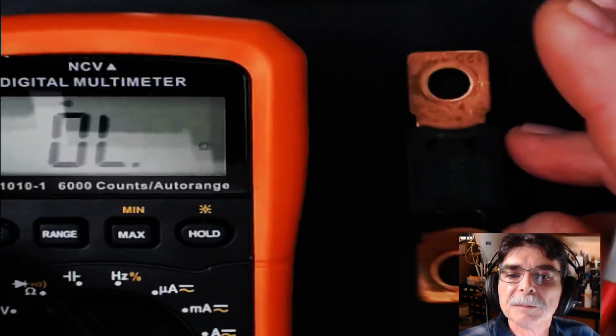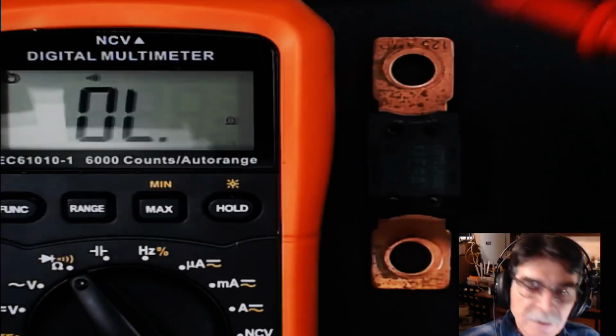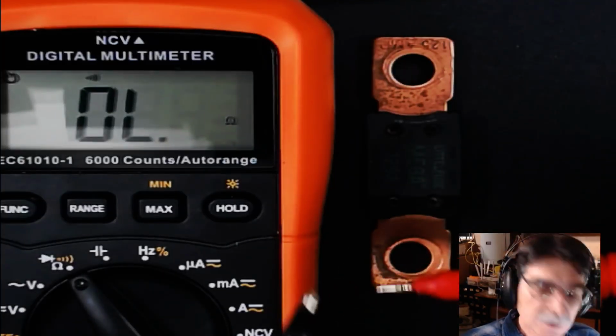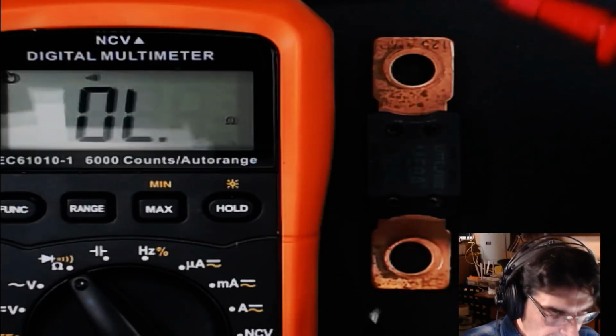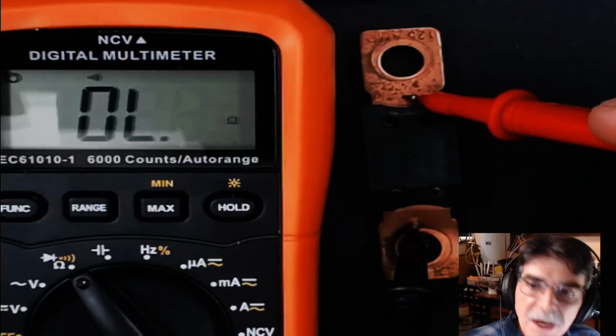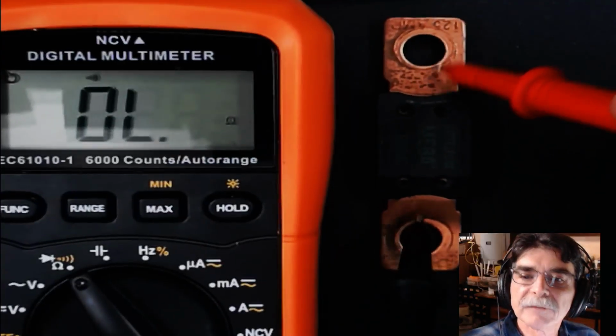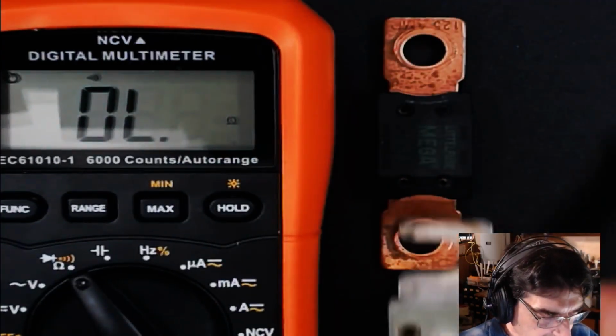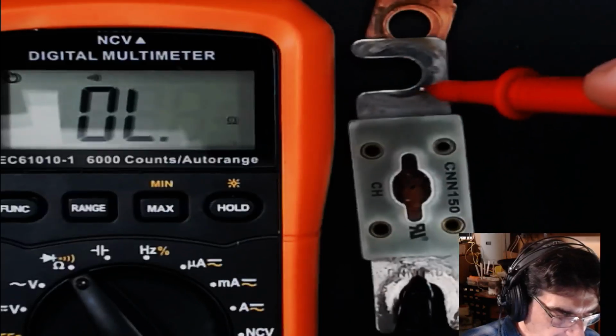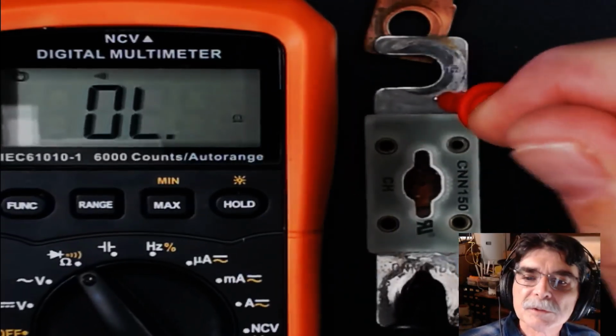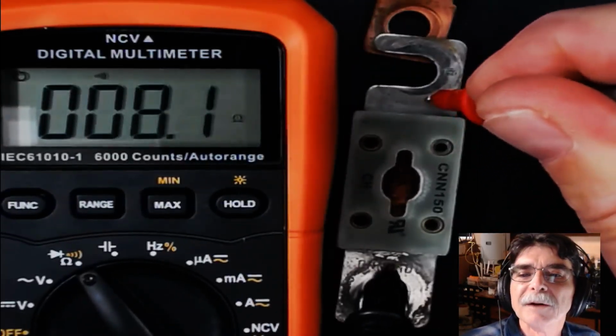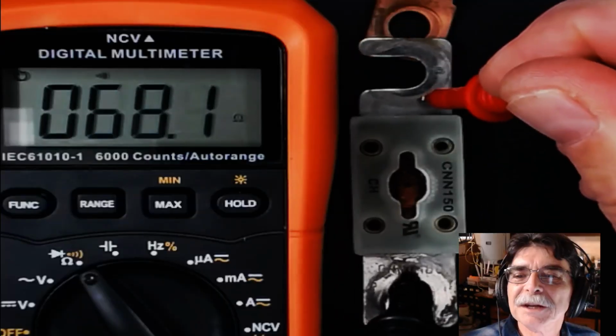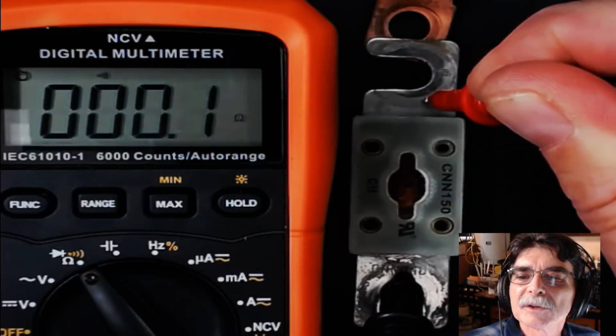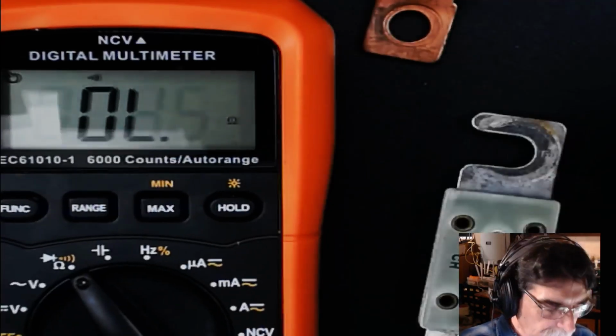So if we bring our meter back into the picture and touch our probes as always, making sure it's reading continuity, and I touch either side of the mega fuse, I have an open. If I touch either side of the ANL fuse, it's also open. No, I just had to get through the corrosion on it. So this is a good fuse, where the mega fuse isn't.